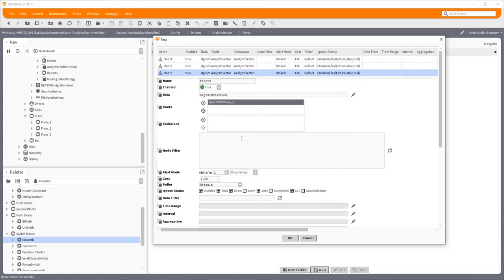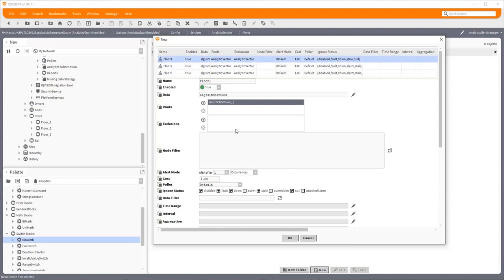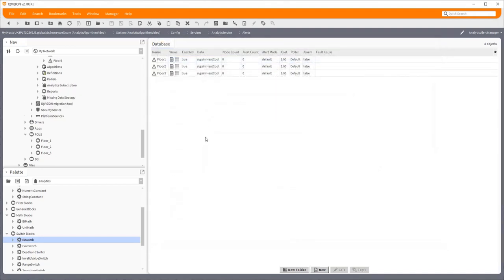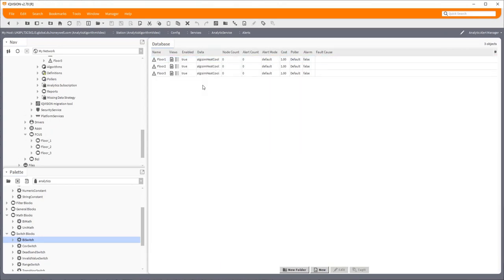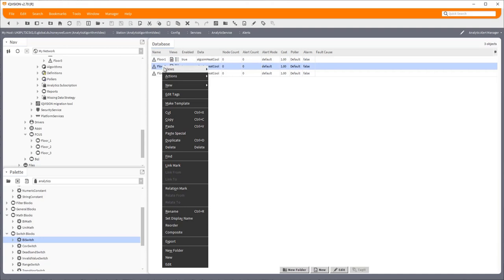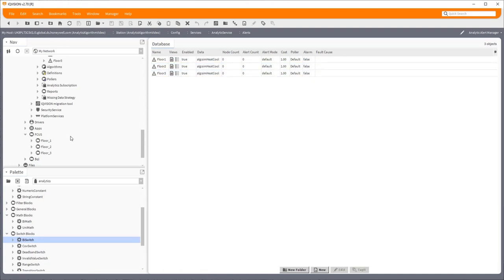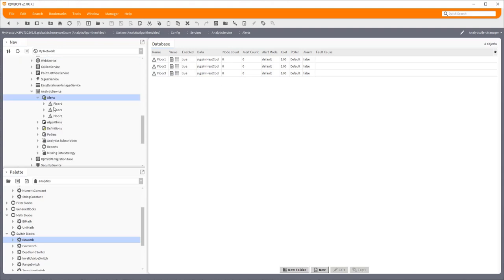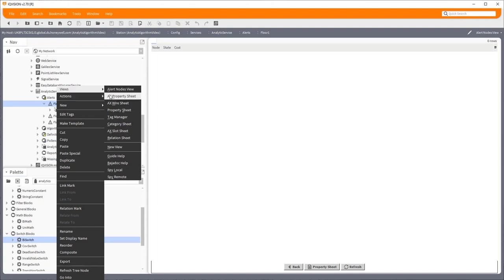Now for floor one I want to go to floor one, so this sets the scope for that particular algorithm. It's only going to look from that folder down, and I want to do this so that I can be a little bit more picky perhaps where the alarms go or some such, which you'll see soon. I could just have one big alert system of course, but I'm going to be a bit more targeted than that. I'm going to ignore all of these extra states because I am dealing with fake plant, so I am going to be overriding things on and off and so on, so we'll just hit okay. Now each one of these we can do a find related data on it, and it should go away and do exactly what I've just asked it to, i.e. find related data.